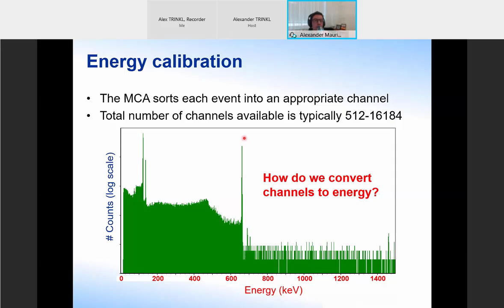And the way you do this is by so-called energy calibration. And this is something you do by measurement of known sources to relate the channel number to a certain photon energy. So you'll measure sources or samples that you know the energy emissions of. You'll measure, for example, americium-241, which sends out gamma at 60 keV. You'll see that, okay, 60 keV gives me a peak in this channel here. Maybe you'll measure then potassium-40, another common nuclide, which gives you a signal at 1461 keV. You see, okay, I know I have this energy. It gave me a signal here. Very nice. Eventually, you might draw a curve through those to get a general relationship between channel and energy.